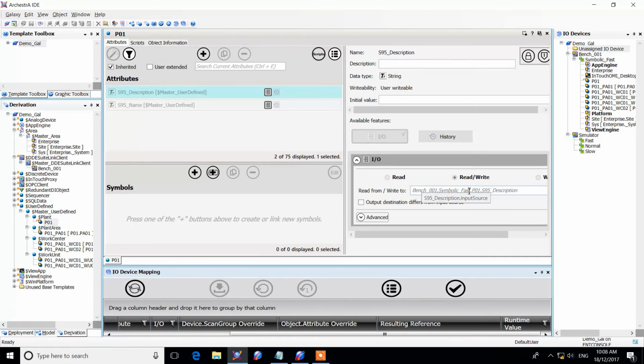So if we're lucky, we now have a DDE SuiteLink object that we tested with the SMC and showed the connection was working to the PLC, and now we have a DDE SuiteLink object name and a topic name that are valid, and we now have the first level of our hierarchy mapped automatically.